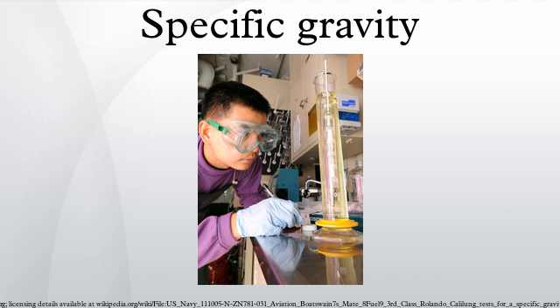In modern laboratories, precise measurements of specific gravity are made using oscillating U-tube meters. These are capable of measurement to 5 to 6 places beyond the decimal point and are used in the brewing, distilling, pharmaceutical, petroleum and other industries. The instruments measure the actual mass of fluid contained in a fixed volume at temperatures between 0 and 80 degrees Celsius, but as they are microprocessor-based, they can calculate apparent or true specific gravity and contain tables relating these to the strengths of common acids, sugar solutions, etc.